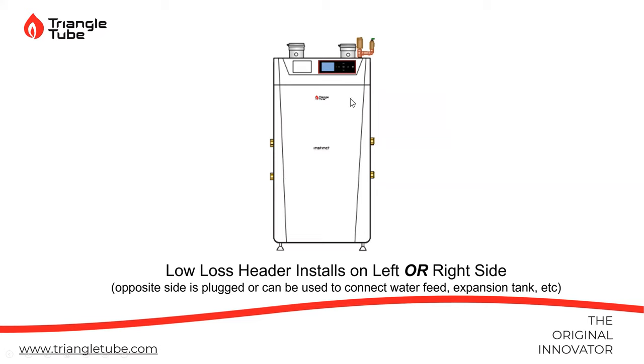The gas line will come straight out through the back of the boiler right here. There's a small male nipple, 3/4-inch. A little trick to keep in mind when you install it: you want to wind these fittings on first before you push this boiler up against the wall. So you're going to want to put a 90 on here. If you come out on the right side and you have a 90 and a 5-inch nipple, that will get you right outside that cabinet, and then you can run your drip leg and your gas line up, down, or over, whatever way you want to go.